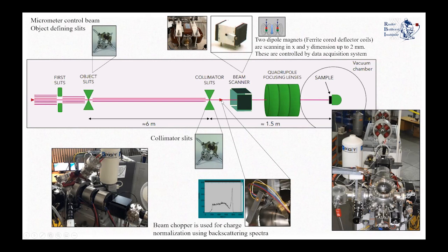This beam chopper provides a means to normalize the beam particle flux. When someone does material analysis, they need to know how many particles hit the target, and this chopper gives us that information. It consists of one stepper motor which moves and intercepts the beam by moving an aluminum sheet with a gold thin layer on top. By measuring the backscattered particles and integrating this spectrum, one can obtain the number of impingent particles.